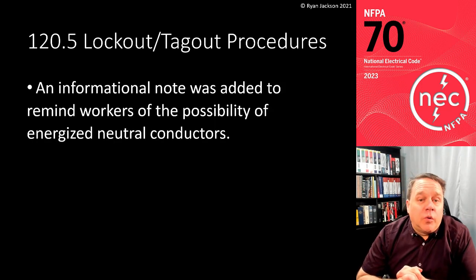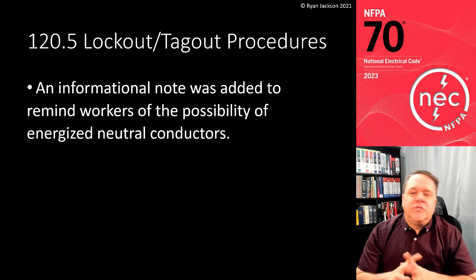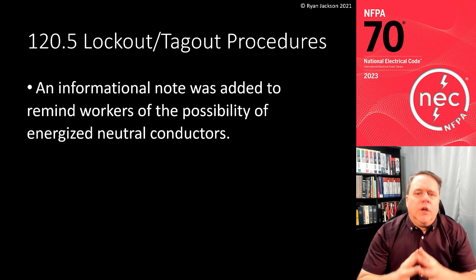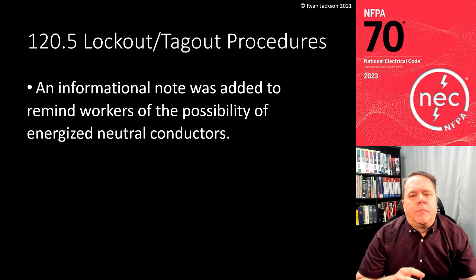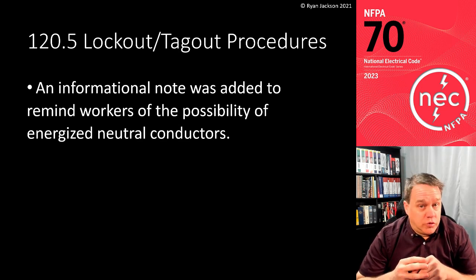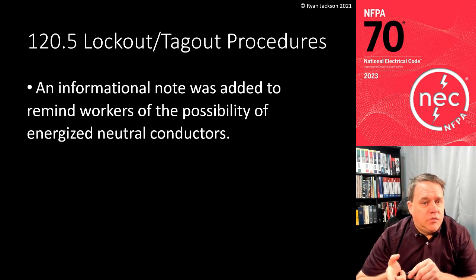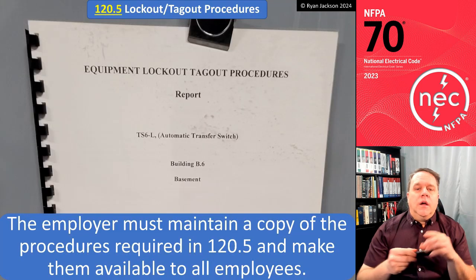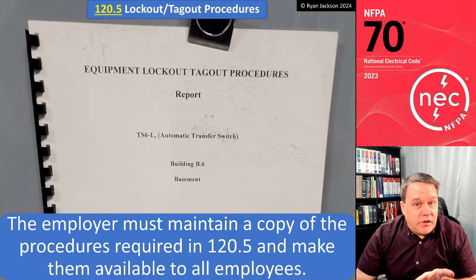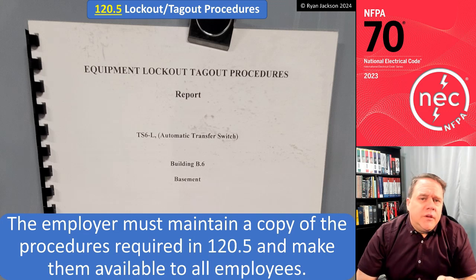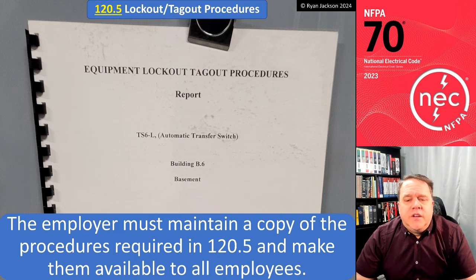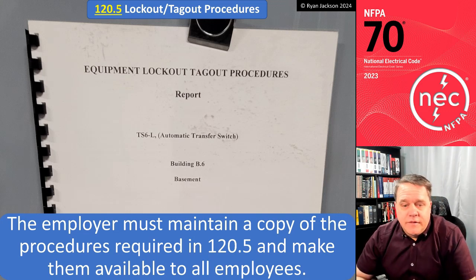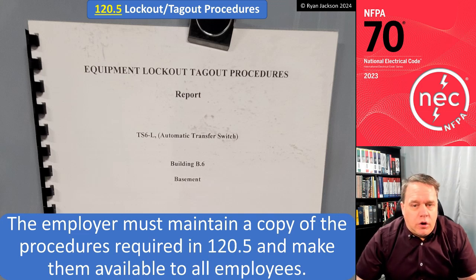All right, 120.5, lockout tagout procedures. An informational note was added to remind workers of the possibility of energized neutral conductors. Not something that comes up too terribly often, but it can. So 120.5, lockout tagout procedures. The employer must maintain a copy of the procedures required in 120.5 and make them available to all employees.